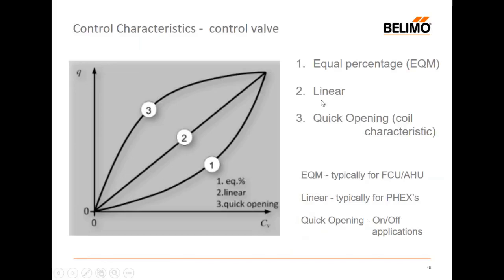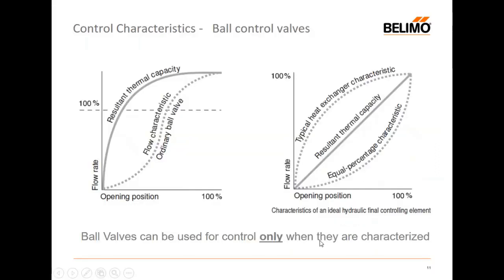If I choose a linear characteristic valve, I'll get this proportionality between the opening of the valve and the flow through the valve itself. So that might be applicable for, say, a heat exchanger. And then I have a quick opening valve in number three. This might be a regular ball valve. I would use this kind of valve for on-off applications. So it wouldn't be suitable for modulating, and nor would a linear valve if I'm modulating a fan coil or an air handling unit. And essentially, that's what we're talking about today.